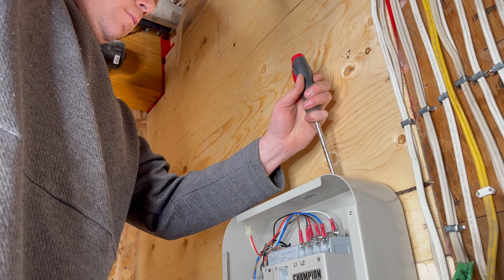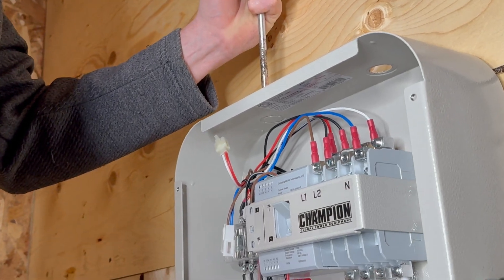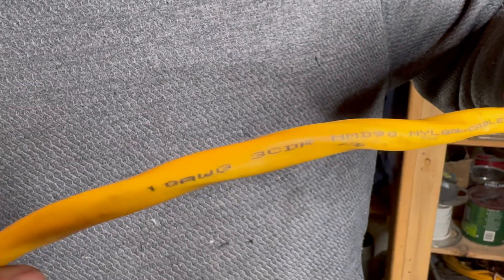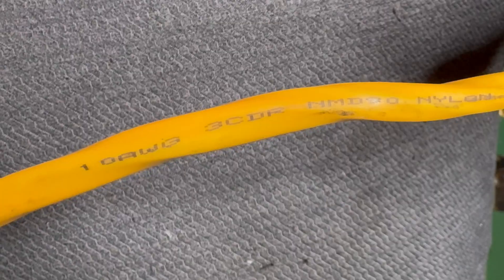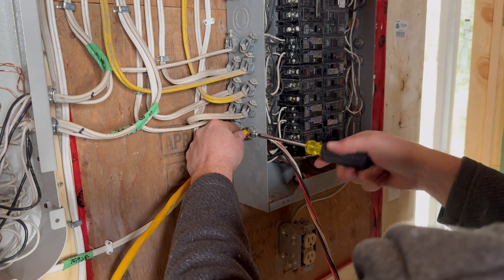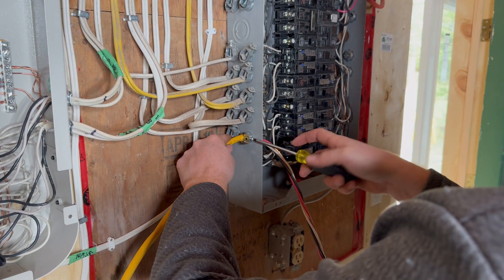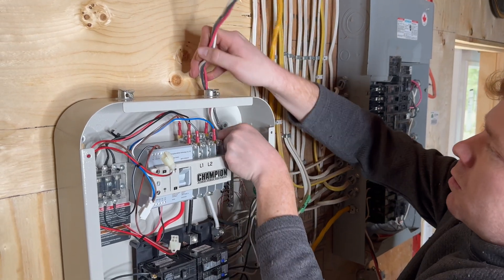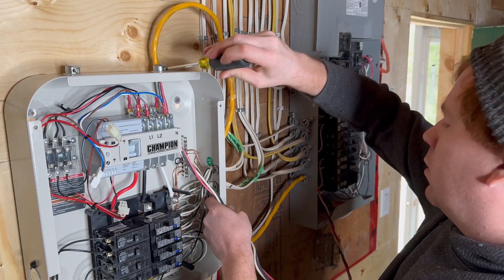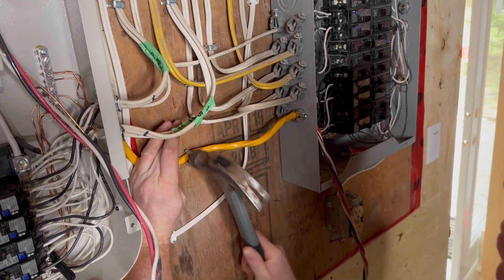Now it's time to start working with some heavier cable. Mark is opening up some knockouts here to allow a cable from the main panel to enter the transfer switch, which provides electricity to your essential circuits when the grid is down. Since we're dealing with a 30-amp transfer switch, we're using number 10 cable and a 30-amp breaker in the main panel. If you were installing the 50-amp model, you need heavier cable and an appropriate 50-amp breaker. Regardless of the size of transfer switch you're installing, you'll need to use double pole breakers, which provide two phases of 120 volts for a total of 240 volts when you need it for something like a stove or a dryer.